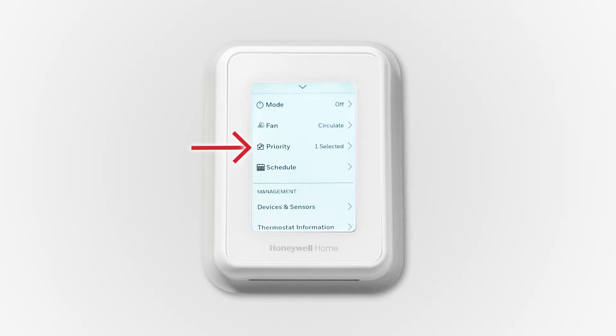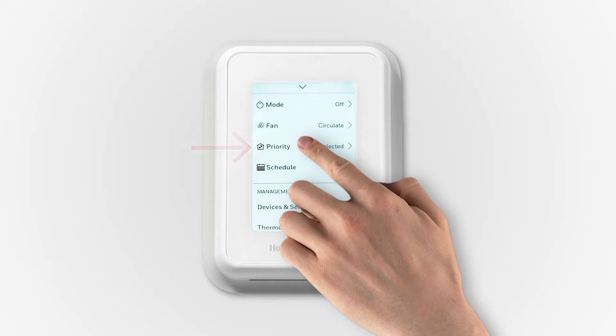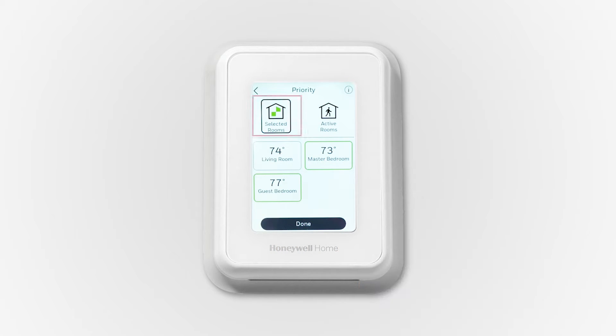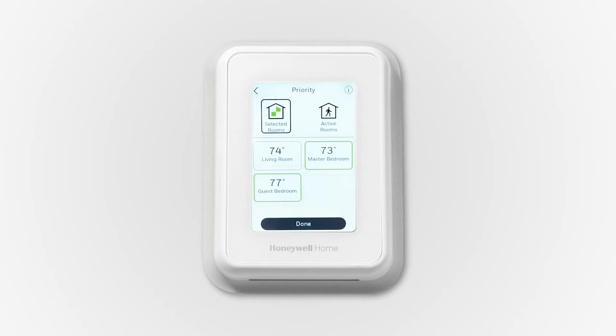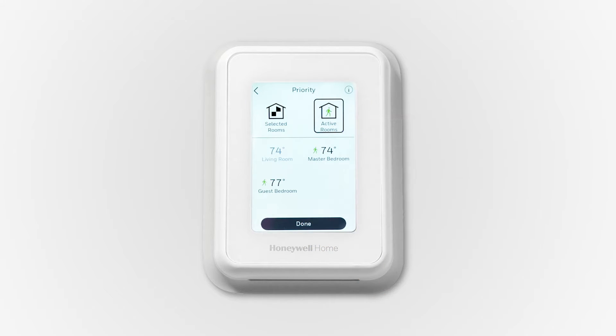Select priority. All of the indoor sensors display. When we select guest bedroom and master bedroom, the thermostat will control to the average of these two selected rooms. Instead of using selected rooms, we may want to control to the average of the rooms where people are — we select active rooms for this.